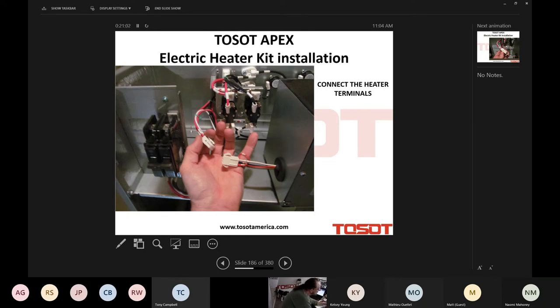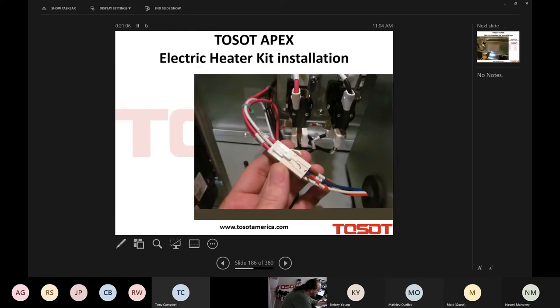You make the connection, the Molex connector of the electric strip to the electrical box. Now that's your power source. That's your power source for the fan coil. You're powering that breaker. And internally now, we took care of everything else. Isn't that sweet? I think it's brilliant, and it is sweet.